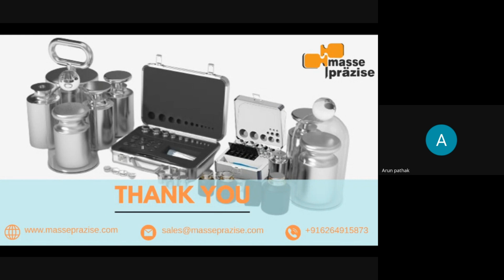Second question is, can we use two different weight kits for one measurement? For example, 3 kg weight, 2 kg plus 1 kg kit. Yes, that can be used. You can use multiple weights, and you can use the certificate value of each weight separately. Suppose you are using a 2 kg weight that has a value of 2000.00, and a 1 kg weight that has a value of 1000.01, then the total mass value of 3 kg will become 3000.01. So you can use multiple weights. There is no issue in that.